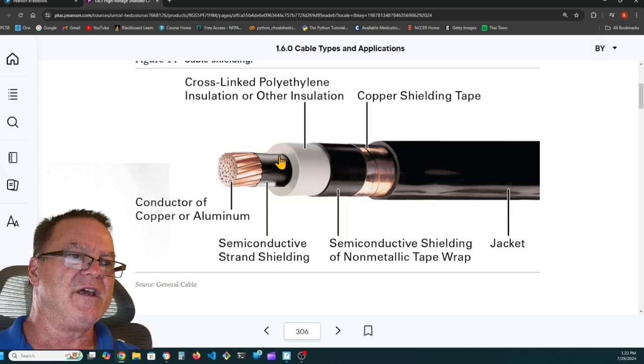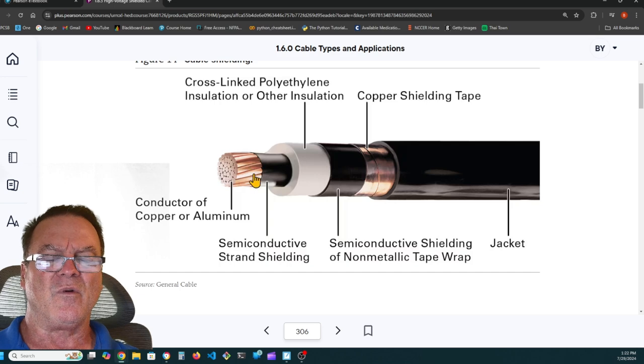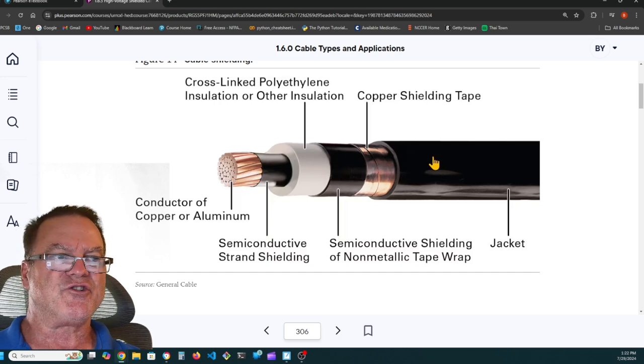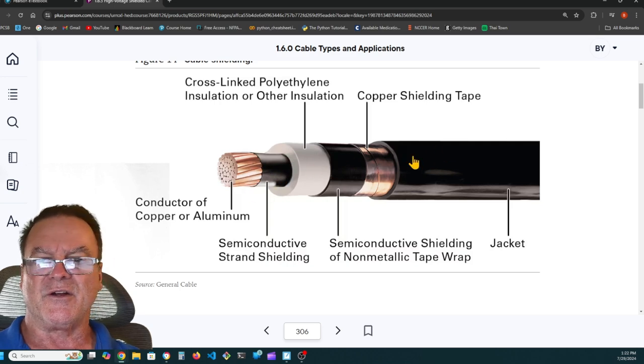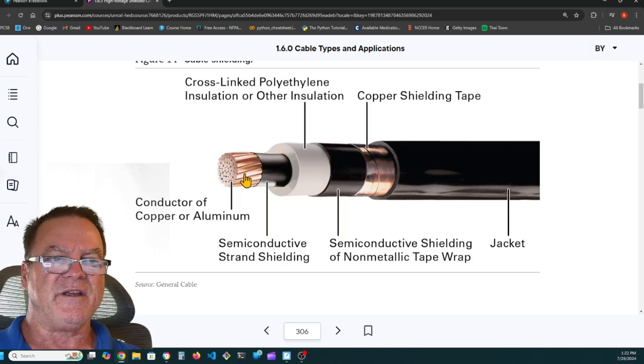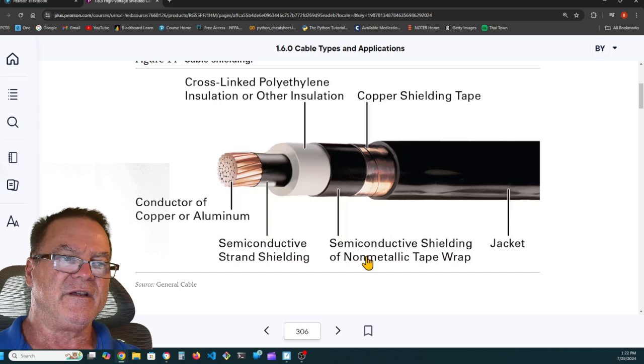When you're terminating this, you have to be very careful and skin these separate layers out individually. And this last layer, when you take this semiconductive material off of the copper or aluminum, you have to use sandpaper or burnishing cloth to get any residue from the semiconductor off of the copper. You don't want it to track back. You especially need to clean this insulator for the same reason. It might have some semiconductive material on it that will allow those stray voltages to track back and try to get to ground. And it may cause the high voltage to jump to ground rather than staying contained in the system. It'll blow out.